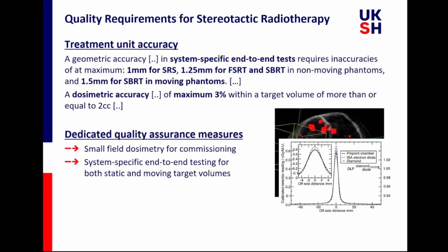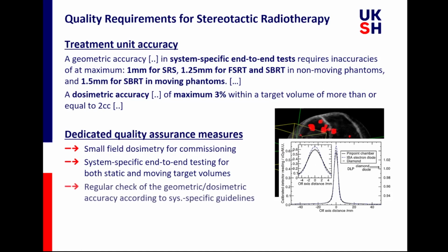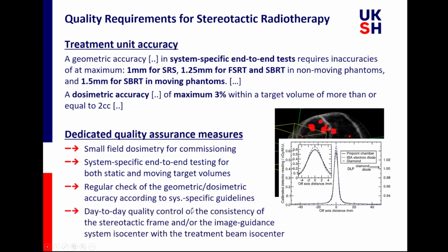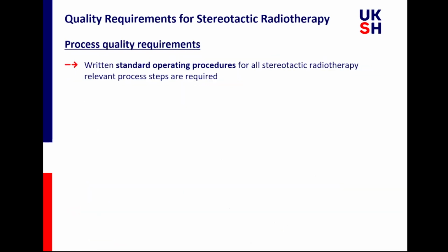So basically, if a tumor is moving and you treat that with some kind of motion compensation technique, we want that to be tested and accordingly check that the accuracy is correct. And of course, this needs to be regularly checked according to system-specific guidelines, and day-to-day quality assurance needs to be done between the image guidance system and the treatment beam isocenter. This is also very important to check that your system is working properly every day that you're using it.